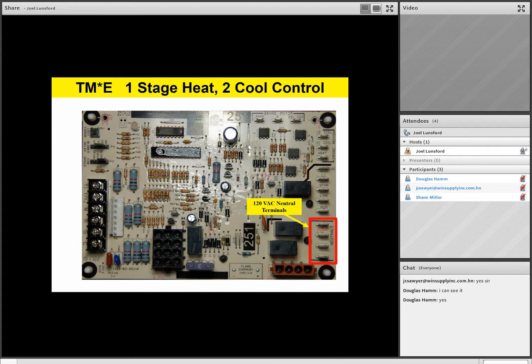As we move around to the bottom of the board, we have an output harness to the hot surface igniter and the inducer fan motor. This is where those components are harnessed in. Now please notice something, team. If you take a look at this control board, you'll notice there's no harnessing or any wires hooked up to this board. The reason we did that is for training purposes. We've taken all the harnesses off so we can talk about all the components on the board.